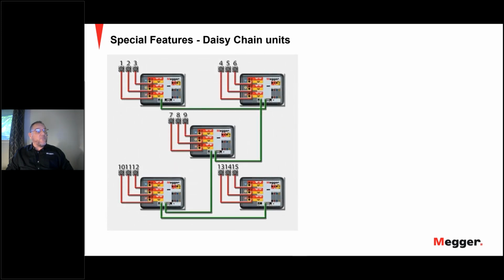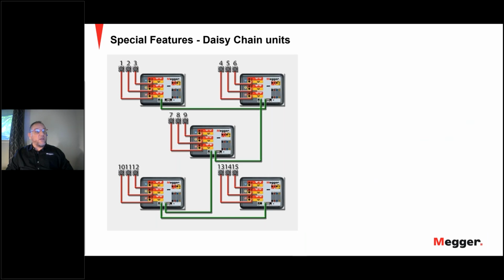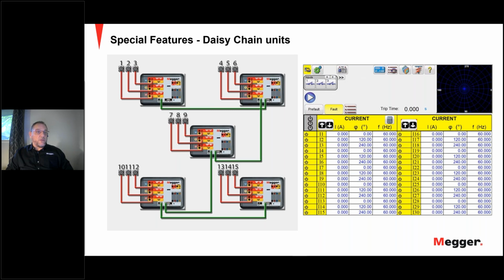Okay, moving on, special features like daisy chaining of units. You can daisy chain up to 5 SMRT 46s, which will then provide you with 15 current channels and up to 20 voltage channels. And the voltage channels can be converted to current to give you up to 30 current channels for testing bus differential schemes.